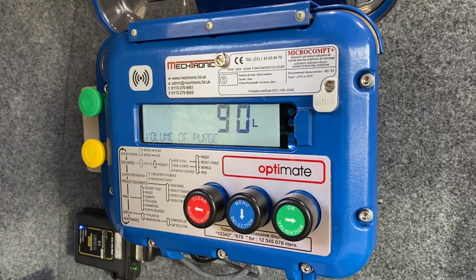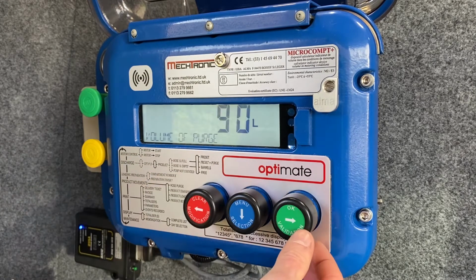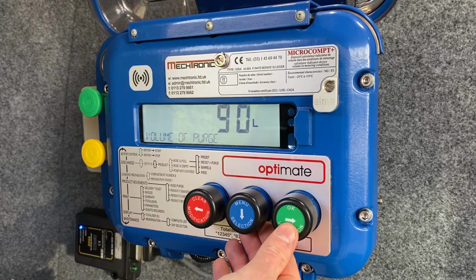The volume of purge is preset from the OptiMate metering system. You can't override that. OptiMate will perform a volume of 90 litres, which will get rid of all the gas oil out of the manifold, pushing 90 litres through, ending on a 100 litre delivery with kerosene in the line for your next kerosene delivery.